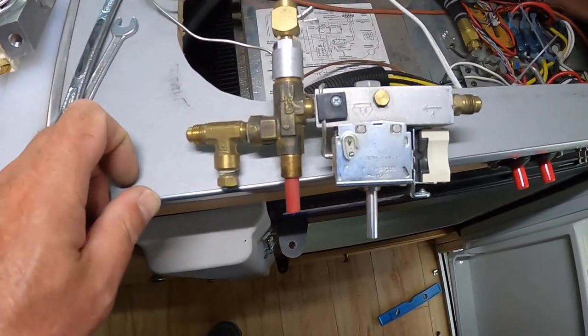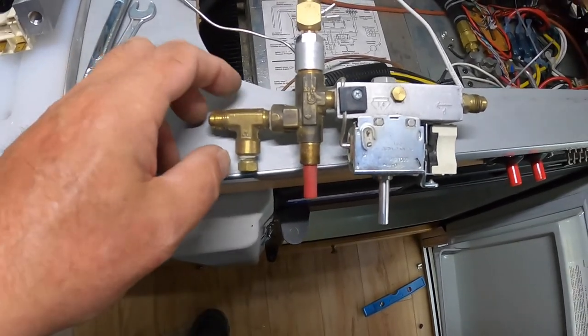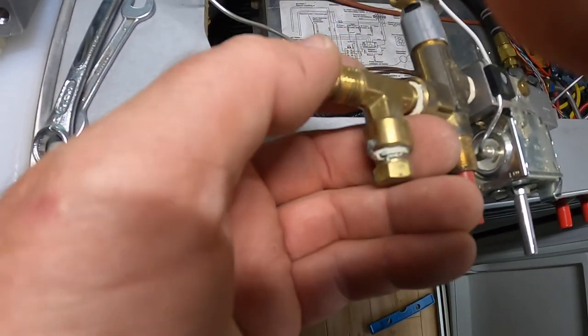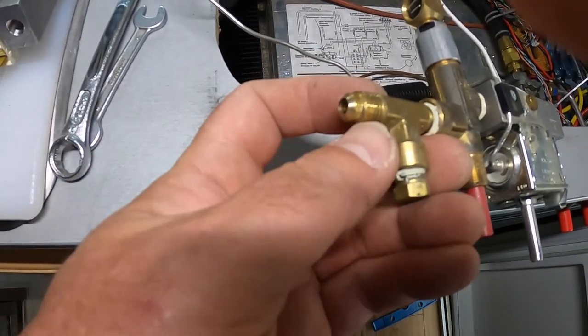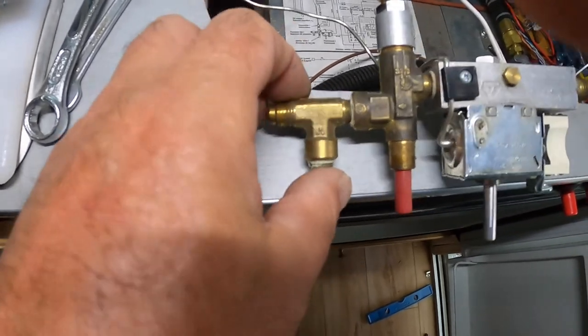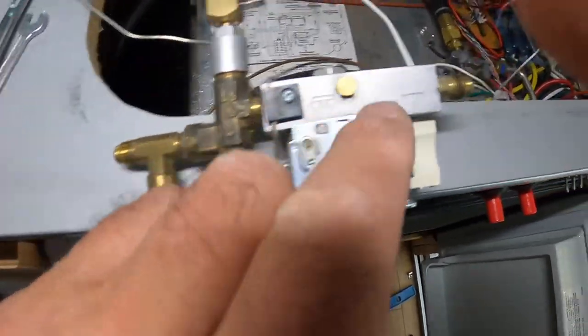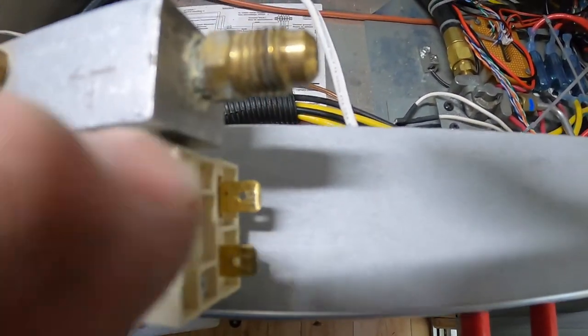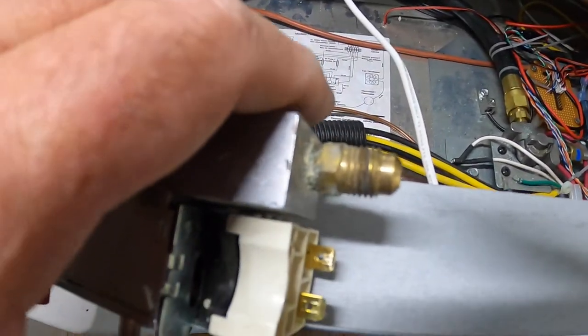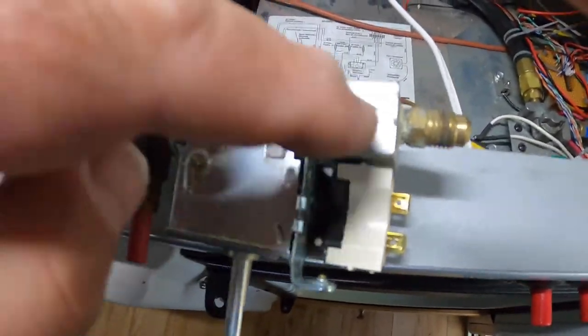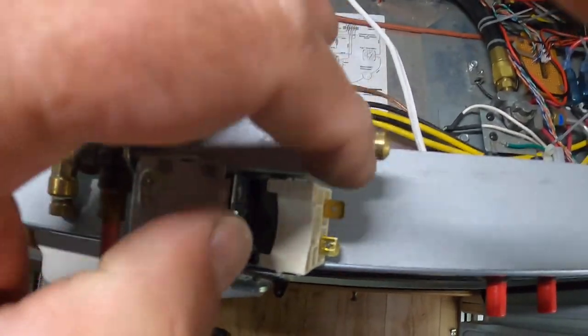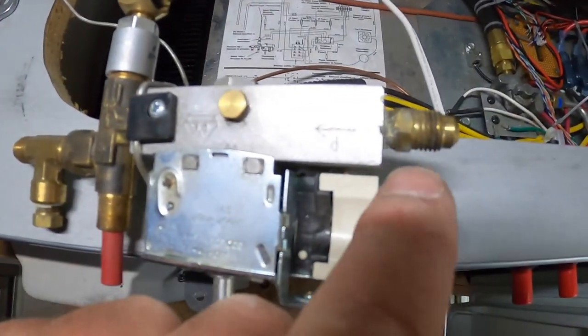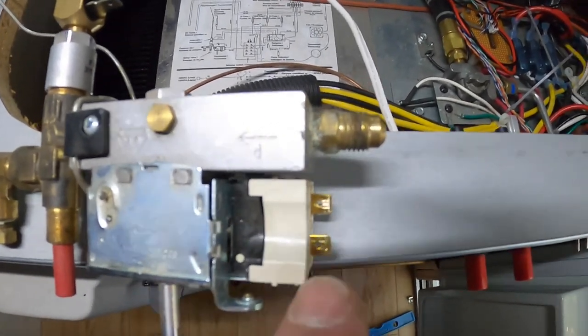Okay, now I know a lot of you are in love with Teflon tape, but this is not a place for Teflon tape. These are compression fittings. And you see that there's no tape on there. There's no goop on there. There's no nothing. It doesn't require it. So the output and the input are compression fittings. But on the edges here, if you look, they have some pipe joint compound. Just a little bit. Not much. You don't want to get pipe joint compound into the valve assembly. But just a little bit on the threads on each side of this. No Teflon tape. Pipe joint compound. It's what you want to use.